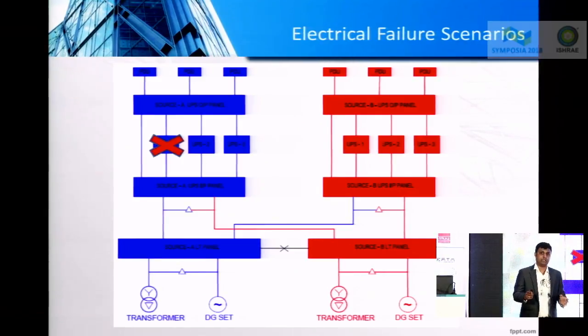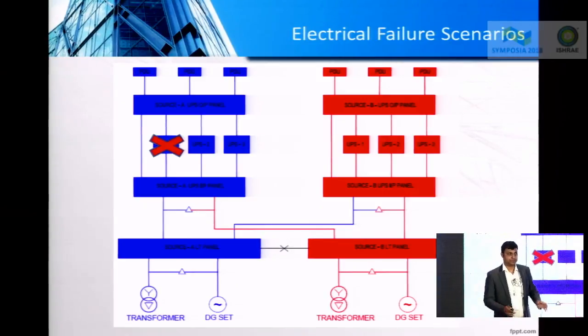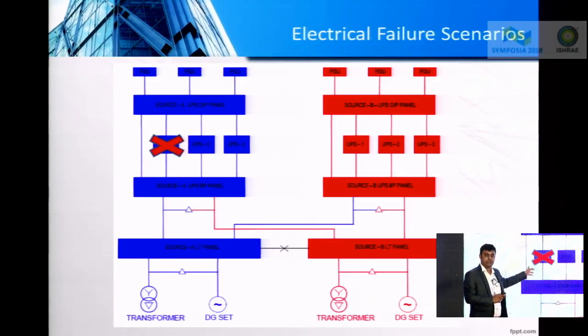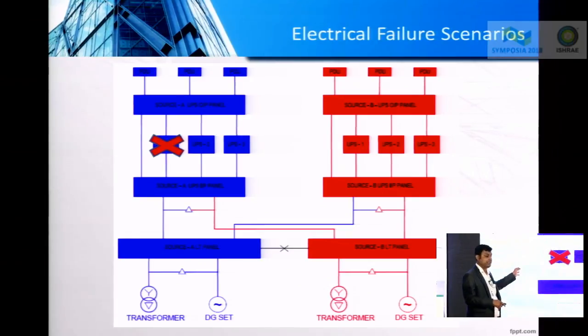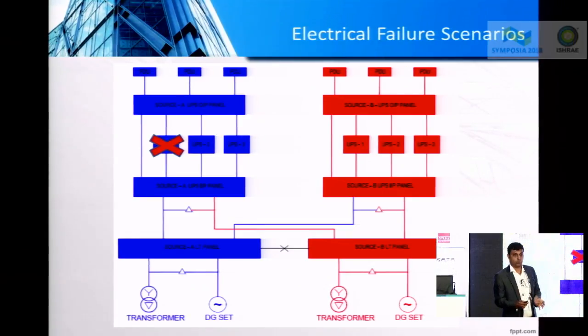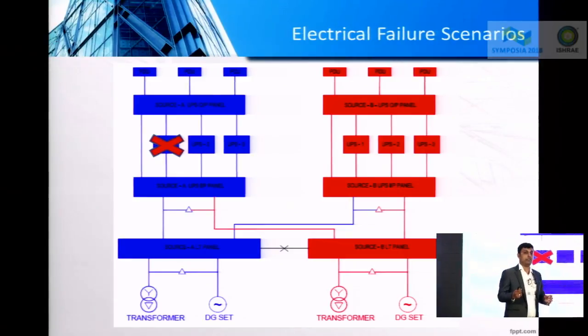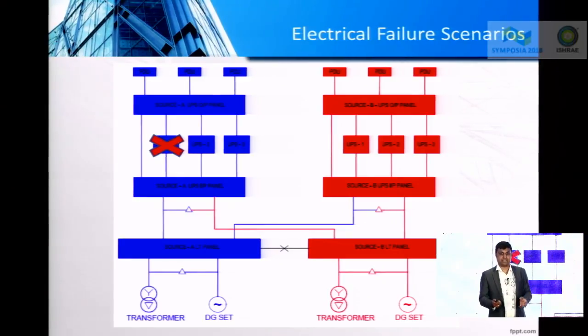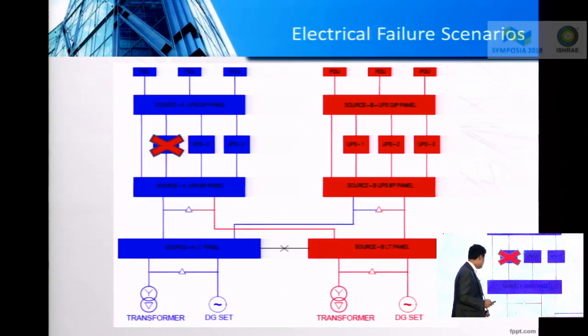In a normal operating mode, 50% of the load is on source A and 50% of the load is on source B. If I create a failure scenario of a UPS, which normally runs at 30 to 33% of its capacity or less, and I fail one UPS, the other two UPS should be able to take care of the load. So what we are trying to do is find the weak links and worst case scenarios, and validate the redundancy level of your data center. Same thing, we can do it for source B.